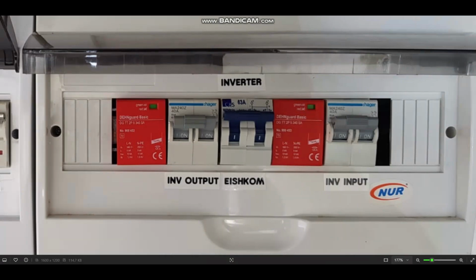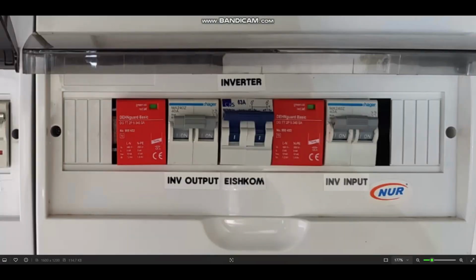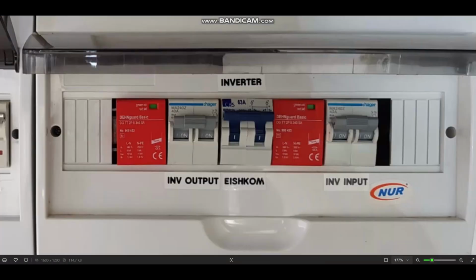Then what you have is another surge protector for the return trip, for the channel supplying power from your inverter back to your main distribution board. What for? Well, similar principle. In the event that your inverter malfunctions, it sends out bad voltage, this little 1,800 Rand surge protector will protect the appliances on your main distribution board. So your gate motors, your fridges, your televisions that might have needed replacing in the past because your line got hit by lightning, this will serve the same function.